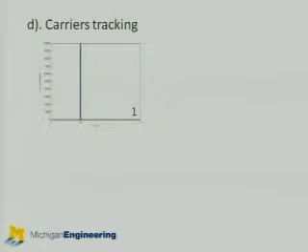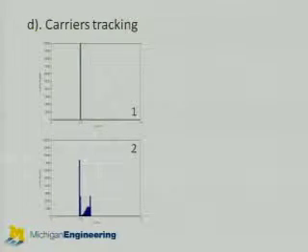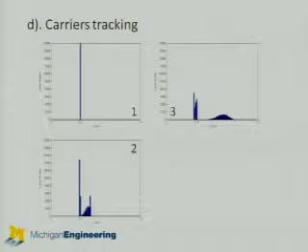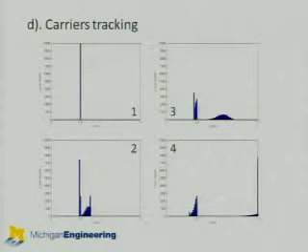So at the beginning, the interaction happens at a depth equal to 0.5 centimeter. And then the electrons drift to the anode side, which is the right side of the diagram, and the holes drift to the left side. We can see here, electrons have a much higher mobility than holes. Then, because of the fast trapping and detrapping time, the electrons form something like a Gaussian distribution. But we can see the holes are trapped around where the interaction happens. Finally, when the electrons are collected at the anode side, the holes are still around where the interaction happens.